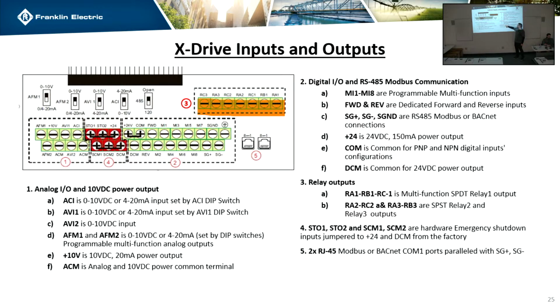STO1, STO2, and SCM1 and SCM2 are hardware emergencies that don't require any program, and that's these over here. They're jumpered from the factory. The only one I've seen used so far is STO1 and STO2, which was used for a fire suppression system. But if you pull that, there's no amount of programming that will get the drive to run. It's DOA until it's replaced.